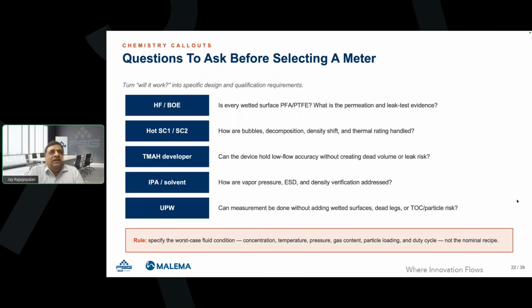In the case of hydrofluoric acid, is every wetted part PFA? That's very critical. And then what is the permeation? So the thickness of the PFA tubes, or if you're looking at an ultrasonic flow meter, where the piezos are kept, which generate the ultrasonic sound, and how thin the PFA layer is between the piezos and the fluid path. Those things can lead to permeation risks. One is that the lifetime of the product can come down, and second, it's a hazardous fluid. That's more of a concern, right? So in such applications, one could adopt, as I mentioned earlier, a purge. You can keep the product under elevated pressure such that permeation is avoided.